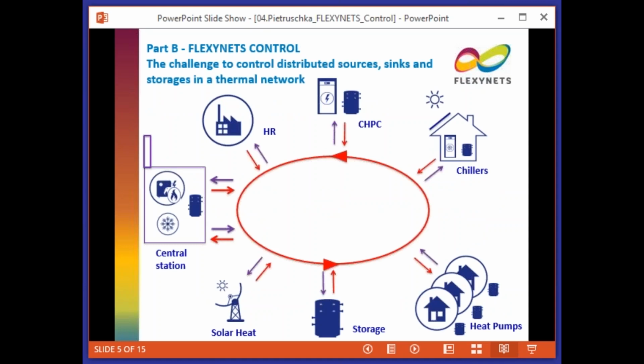So what is the problem? We have a ring structure, and connected to this we have different storage possibilities. We have buildings which require heating energy for domestic hot water and space heating, typically connected to this low temperature heating network by heat pumps, which increase the temperature from the low side to a higher level required for heating and hot water. We can also connect chillers or waste heat from chillers to such a network, rejecting heat via the thermal network. So here we feed in heat to the network, here we take out heat.